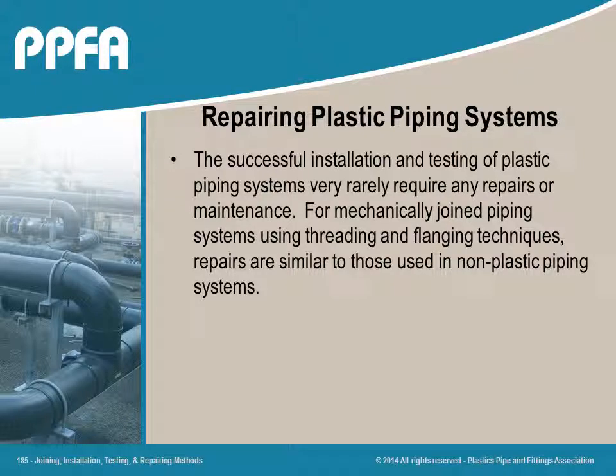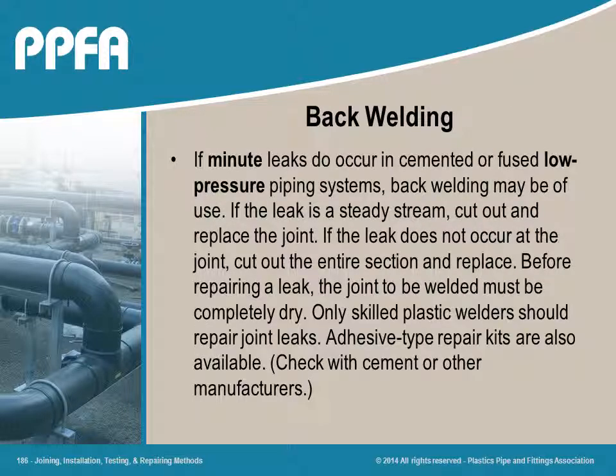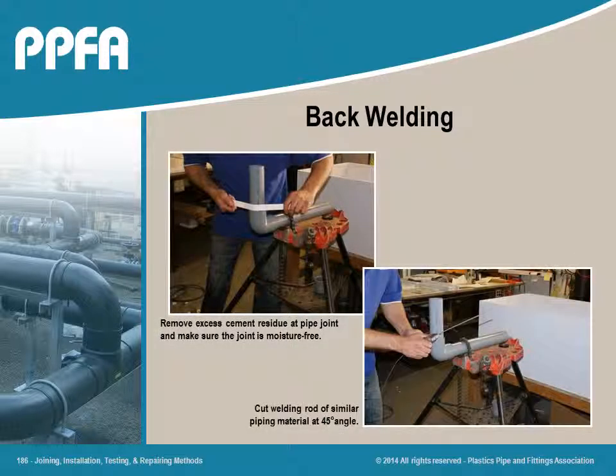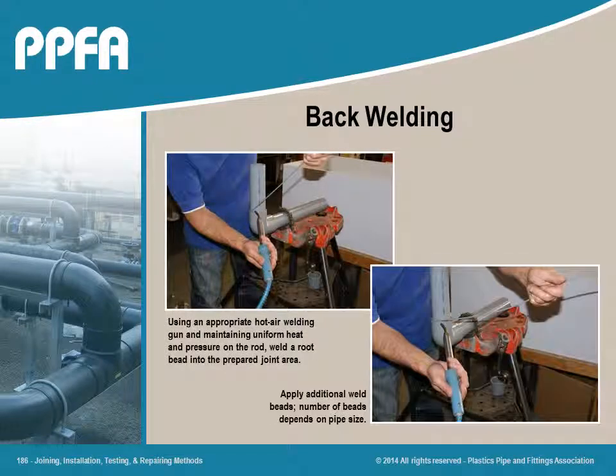When a thermoplastic piping system is properly installed, there is little likelihood that repairs or future maintenance will be required. If maintenance is required, use standard repairing techniques. If very small leaks occur in solvent cemented or heat fused joints, back welding by an experienced welder may be capable of providing a successful repair. Make certain before beginning back welding that the joint area is moisture free. The diameter of the welding rod and the number of weld beads depends on pipe diameter size.